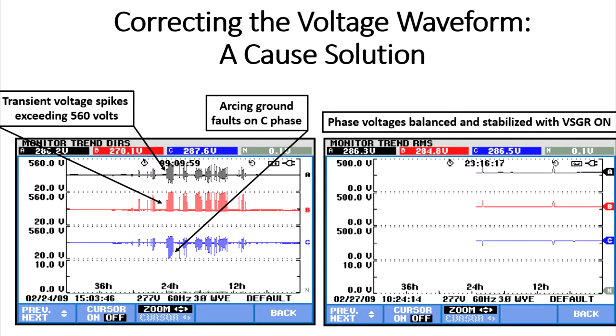You'll see on the blue phase C here, the lines are going down, so the voltage was being pulled down towards ground. And those are called arcing ground faults. As the voltage on C was pulled down, it would cause A and B to be pulled up. So that's where we get the ragged or jagged little lines in there. Each of them are voltage spikes or voltage dips. And again, it was locking up the control system.